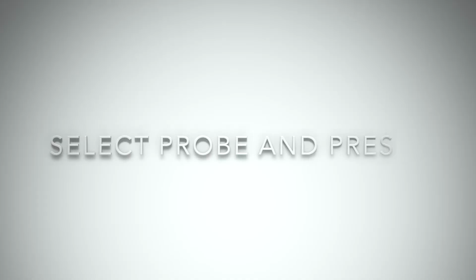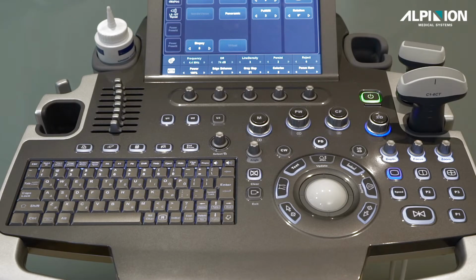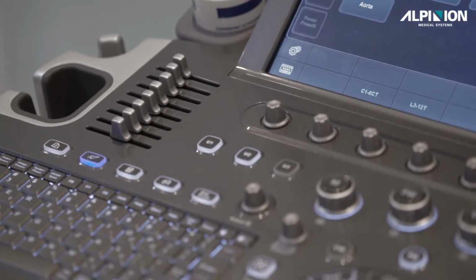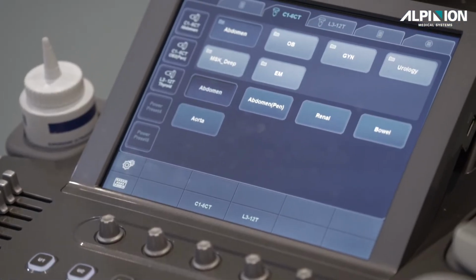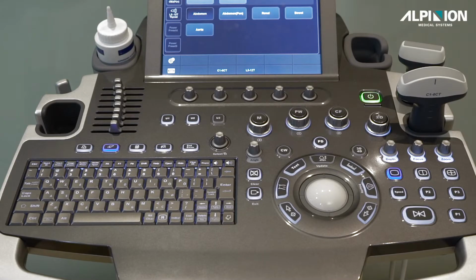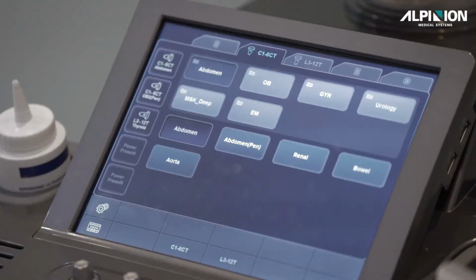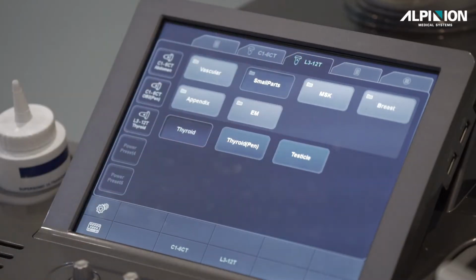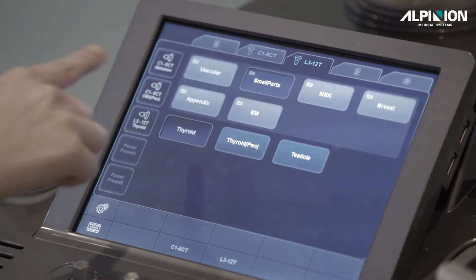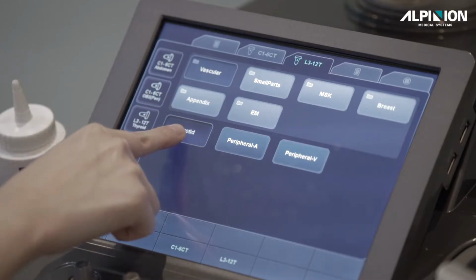Part 4. Select Probe and Preset. To select a transducer and exam type, you will press the transducer button. This brings up the exam type with the different activated probes, their applications, and image presets. For example, if you'd like to do a carotid exam with the linear probe, I will select this L3 to 12T probe, vascular application, and carotid preset.